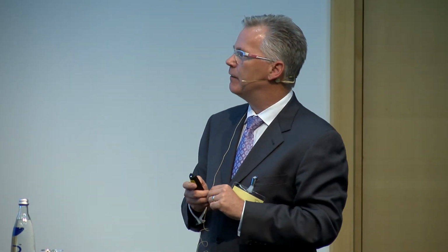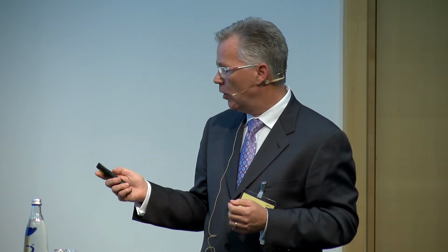In terms of endoscopes, there's some interesting things happening of moving the sensor in from the camera head into the endoscope. It can reduce the head size of the camera, enables it to become one unit. Chip-in-tip technology, that's moving it all the way to the very end of the endoscope, the image sensor, such as in the single lens that I mentioned before. This allows for depth of focus across the entire working area and a range of working distances. You can imagine I've been talking about more rigid endoscopes, but this has application as well in flexible endoscopes and has the great benefit of no lens in the shaft, like a rod lens system, which means low maintenance and lower cost.